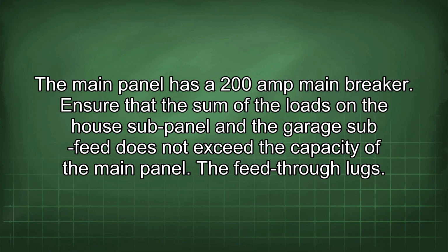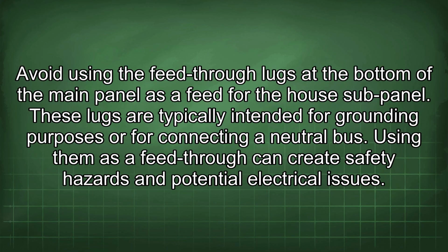The main panel has a 200 amp main breaker. Ensure that the sum of the loads on the house sub-panel and the garage sub-feed does not exceed the capacity of the main panel. The feed-through lugs. Avoid using the feed-through lugs at the bottom of the main panel as a feed for the house sub-panel. These lugs are typically intended for grounding purposes or for connecting a neutral bus. Using them as a feed-through can create safety hazards and potential electrical issues.